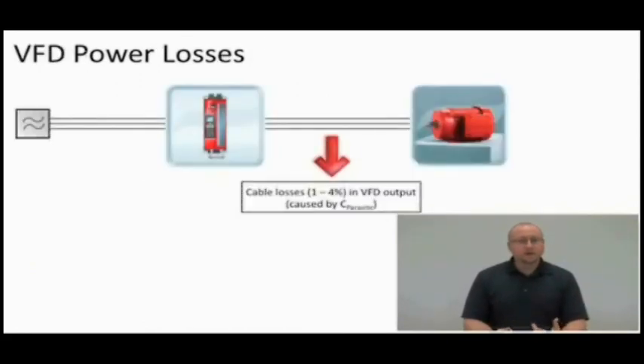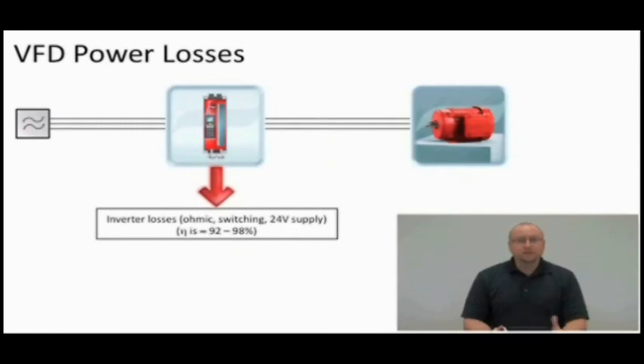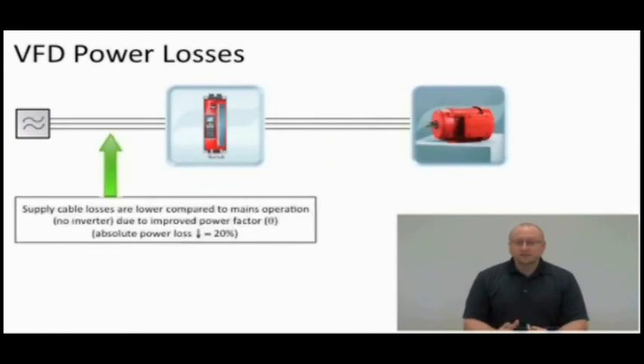We also have some cable losses in between the inverter and the motor. We talked about that. We can have some parasitic capacitance losses also. The inverter has losses, so there again, there's another power loss in the system. But oddly enough, in the cable between your supply and the inverter, you actually gain some energy there. Remember when we were talking about power factor earlier? If you directly run your cable into the motor, it is a very inductive load.